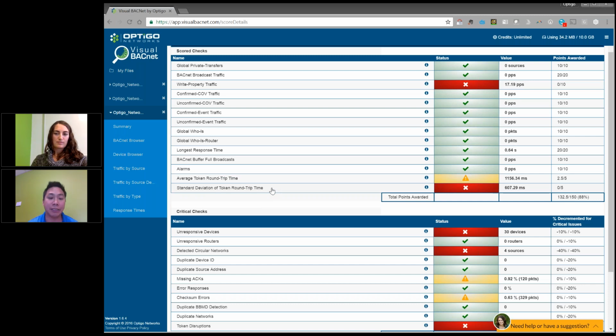The interesting one here is standard deviation, the difference between the longest time and the shortest time around the loop. If your system is consistently busy, you've pushed the limit but you're still within it, you'd have a very high average time but a very low standard deviation. You'd consistently be doing a lot of work. That's okay, it just means you don't have a lot of headroom, you can't add a lot more programming, data polling, or devices, but you're doing fine.